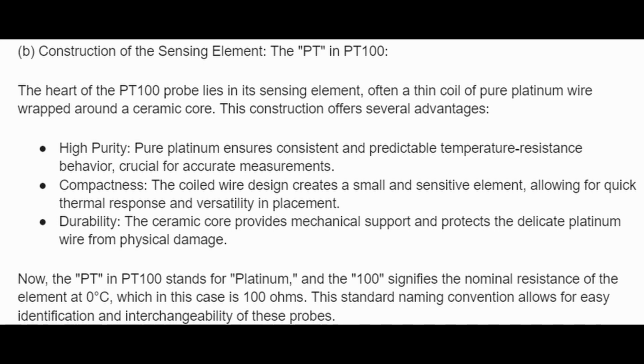Compactness. The coiled wire design creates a small and sensitive element, allowing for quick thermal response and versatility in placement. Durability. The ceramic core provides mechanical support and protects the delicate platinum wire from physical damage. Now, the PT in PT100 stands for platinum, and the 100 signifies the nominal resistance of the element at 0 degrees Celsius, which in this case is 100 ohms. This standard naming convention allows for easy identification and interchangeability of these probes.